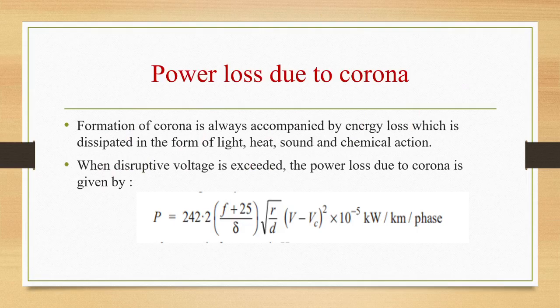Now let us see the power loss due to corona, the third important term. Formation of corona is always accompanied by energy loss, which is dissipated in the form of heat, light, sound and chemical action. So some amount of energy will get lost whenever corona is formed. Energy loss will be dissipated in the form of heat, light, sound and chemical action.